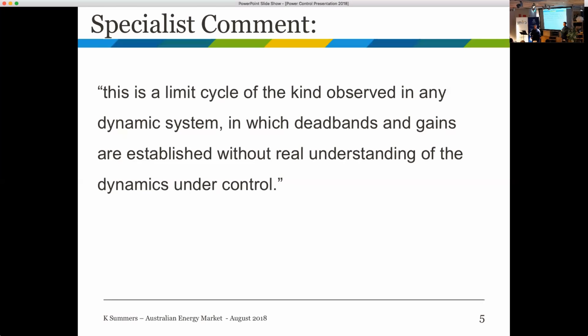But the inertial response is inherent, it's not done within the control system. Yes, that's right, it's an uncontrolled action, a physical response. So it doesn't have anything to do with setting up deadbands or anything. But the mechanical energy into the machine to arrest it slowing down is a control action.